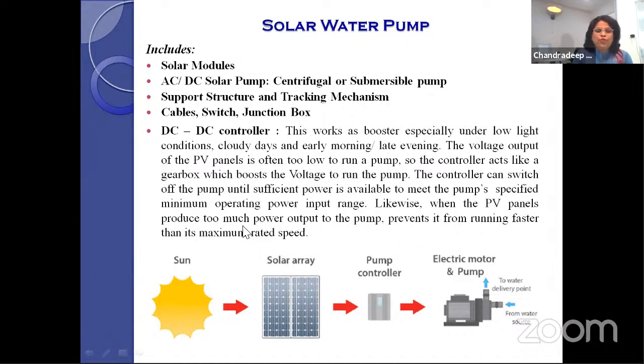Likewise, when the PV panels produce too much power, the controller prevents the pump from running faster than its maximum rated speed. If the pump module is supplying more than 25, sometimes 30 volts, the pump runs faster, and that is also a disadvantage to the pump. In that case also, the DC to DC controller handles all the fluctuations in the input and gives output in a proper way to run and protect the motor. So this is a basic description of a solar pump, whether you are using a centrifugal or submersible pump. This is how a solar water pump functions. Now we will see individually what about centrifugal and submersible, and also the tracking mechanism.